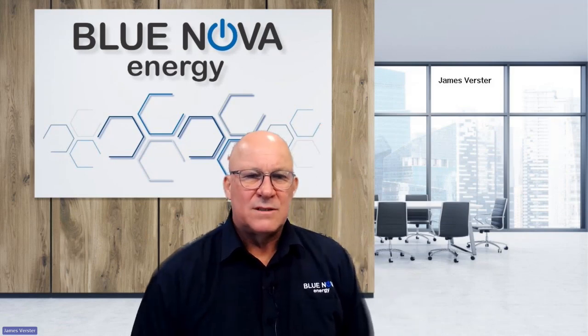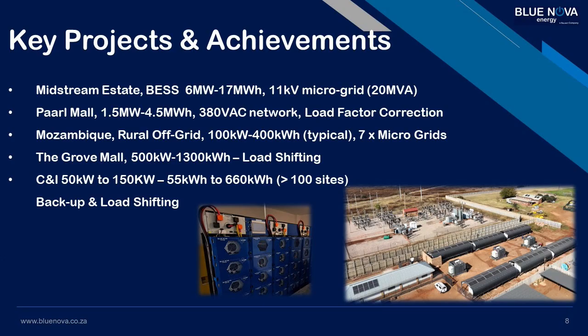We've exported quite a few systems to Mozambique and fully off-grid systems, energizing villages. Mozambique has an intention of providing power to more than 70 villages, and that project is going on very nicely. Also, the Grove Mall, load shifting in Pretoria, where we have a 500 kilowatt by 1.3 megawatt hour system, and also doing this energy cost optimization. Then we have quite a few sites in the C&I space, primarily for backup during power outages, but these systems are now also being used to shift the energy from cheap costs to the more expensive peak periods.